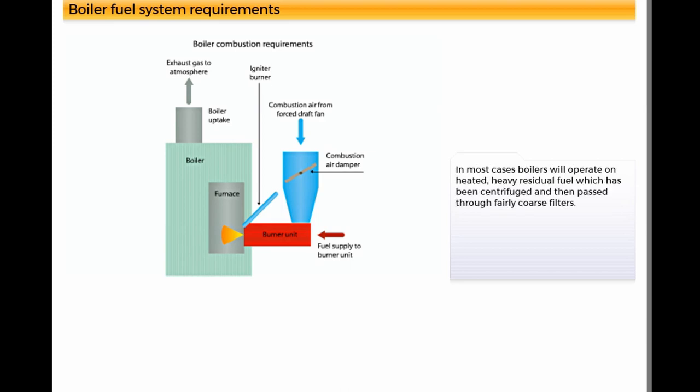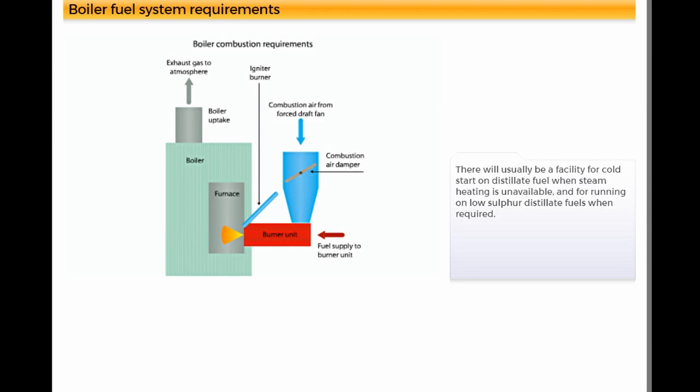In most cases, boilers will operate on heated heavy residual fuel which has been centrifuged and then passed through fairly coarse filters. There will usually be a facility for cold start on distillate fuel when steam heating is unavailable and for running on low sulphur distillate fuels when required.